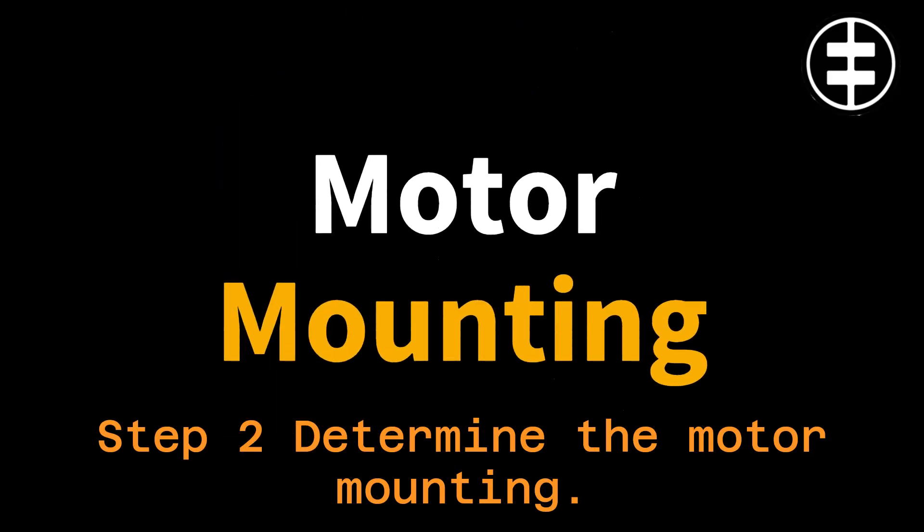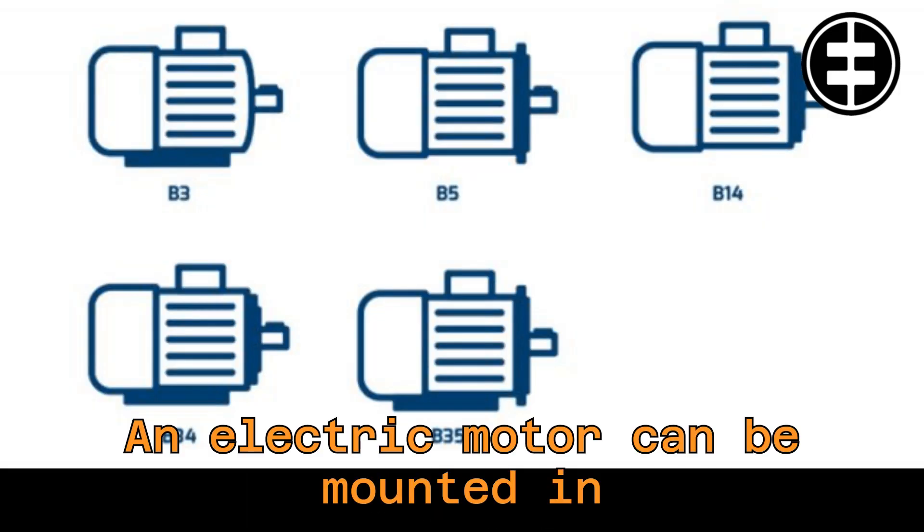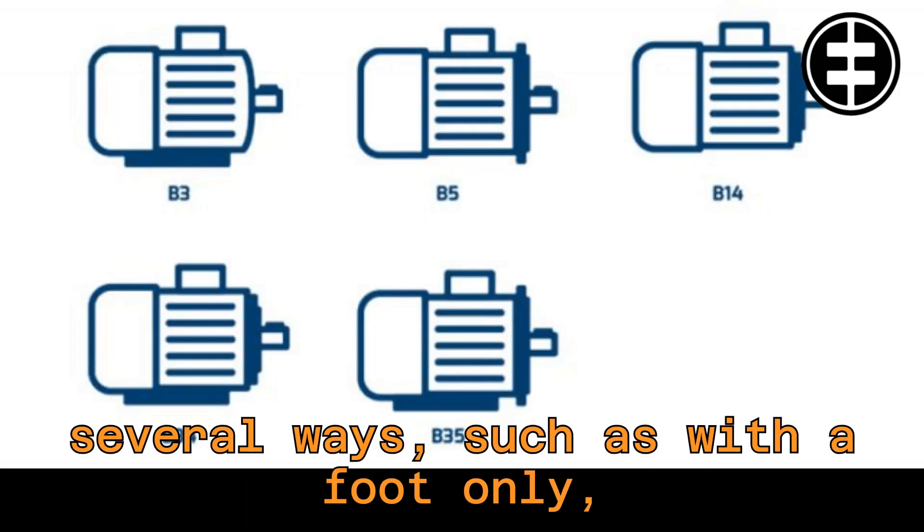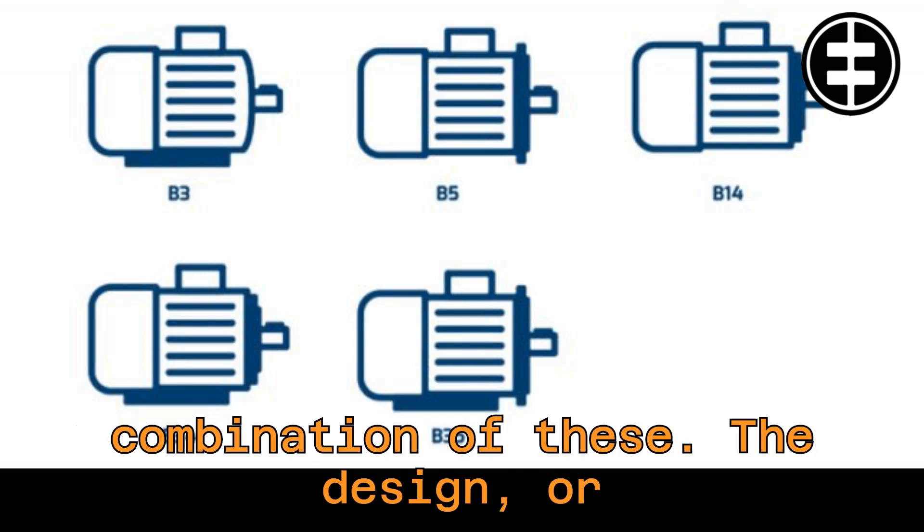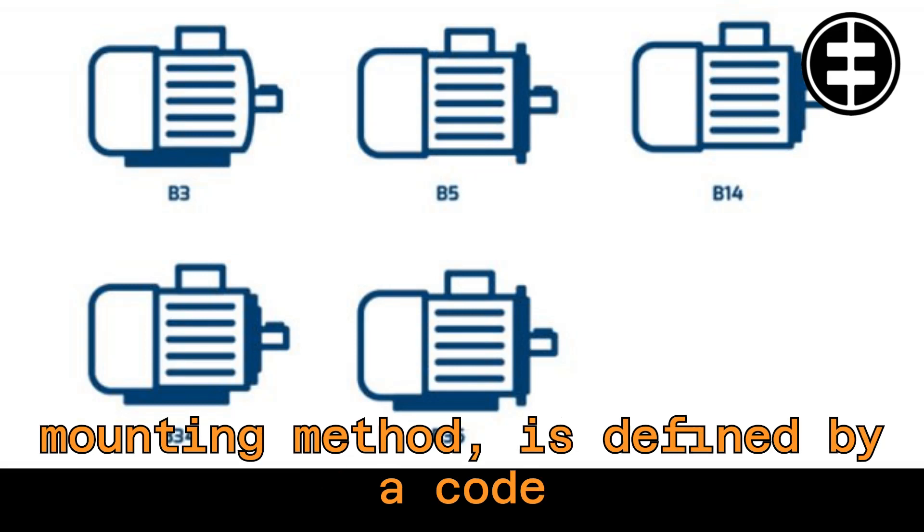Step 2. Determine the motor mounting. An electric motor can be mounted in several ways, such as with a foot-only, an inner flange, an outer flange, or a combination of these. The design, or mounting method, is defined by a code from the European IEC 34-7 standard.